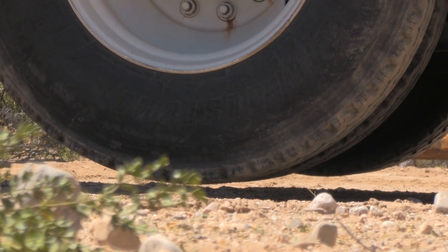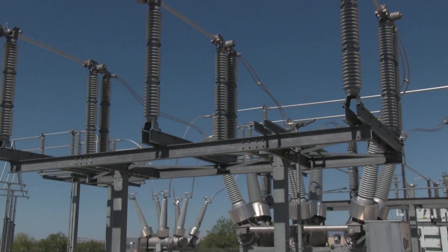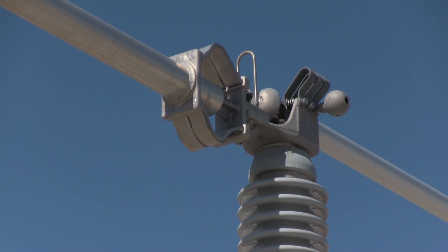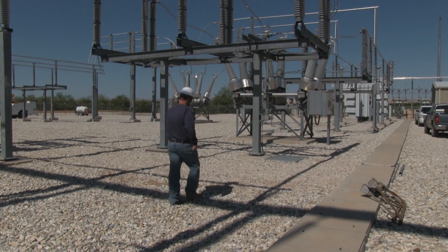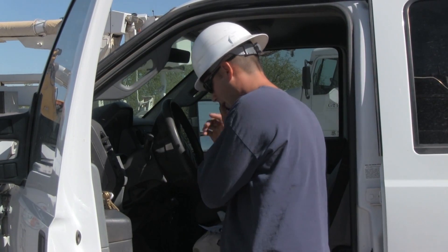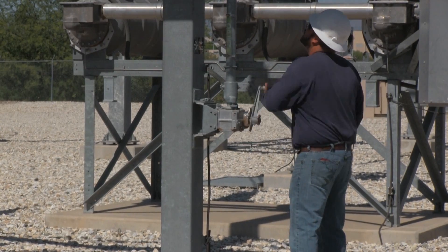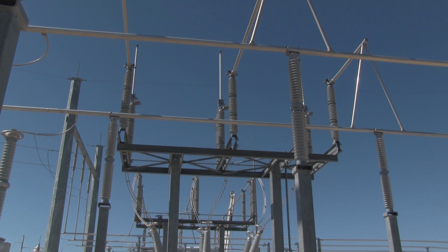Today they'll turn off the power in this section. First, we have to get a clearance on a line — that's called de-energizing it. At the substations on each end of the section, linemen open switches and breakers to keep the current from flowing. At Sahuarita substation, Tony Ferraro speaks with dispatch and Jackson over at New Tucson substation to make sure Jeremy Fenn can safely open the switches.